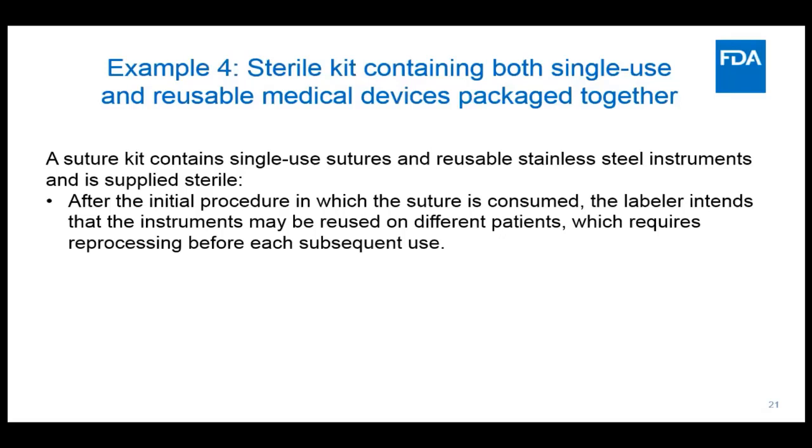So did you recommend that when we do the GUDID submission, for the third part number where these 2 are bundled together, that we would clarify that this is for 2 separate products? You would clarify that in the device description. Yes. Okay, got it.